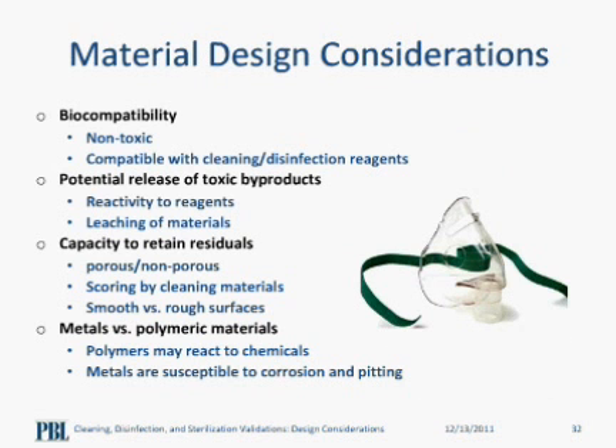If any materials in a device can be adversely affected by the cleaning, disinfection, or sterilization process, we should determine the limit of its reusability. It is recommended to perform a degradation study or exhaustive exposure to determine how many times the device can be reused. These materials should also be evaluated for their capacity to retain unacceptable levels of residuals. For example, porous materials are prone to residual retention as compared to non-porous materials.